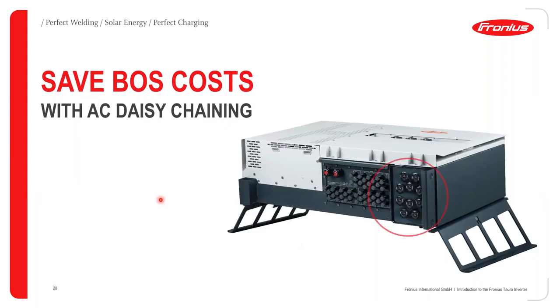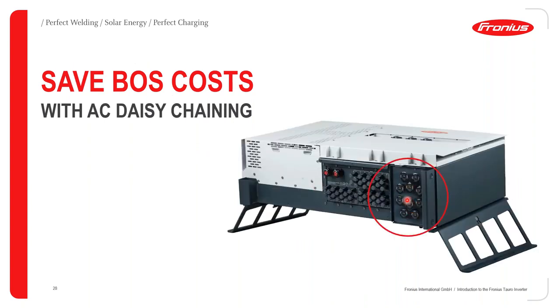So with AC daisy chaining, just to bring the point home, you will have the AC connection area of the inverter, and this connection area will have what we call the in and out. The connection for this particular inverter, for instance, could be the lower part when you're talking about 3 phase connections and neutral plus protective earth. And then the second inverter will also come through the same connection block. This eliminates the need for you to have an AC combiner box.